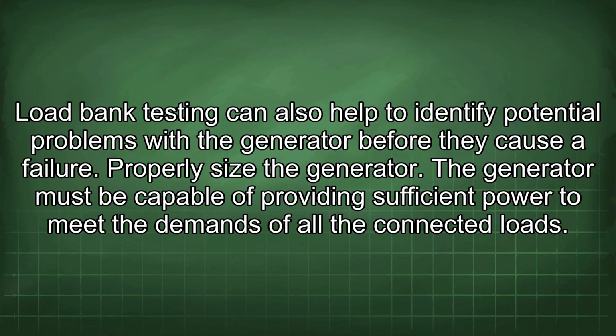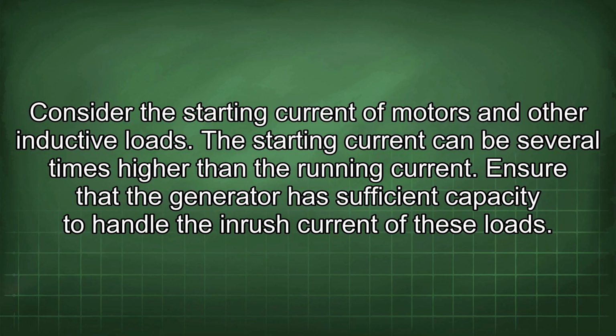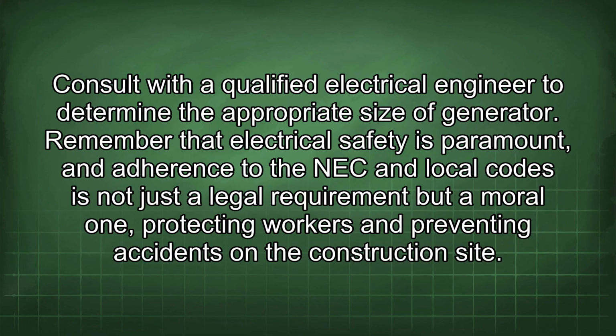The generator must be capable of providing sufficient power to meet the demands of all the connected loads. Consider the starting current of motors and other inductive loads. The starting current can be several times higher than the running current. Ensure that the generator has sufficient capacity to handle the inrush current of these loads. Consult with a qualified electrical engineer to determine the appropriate size of generator.